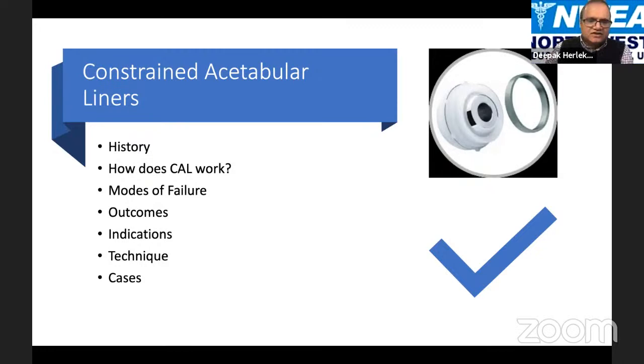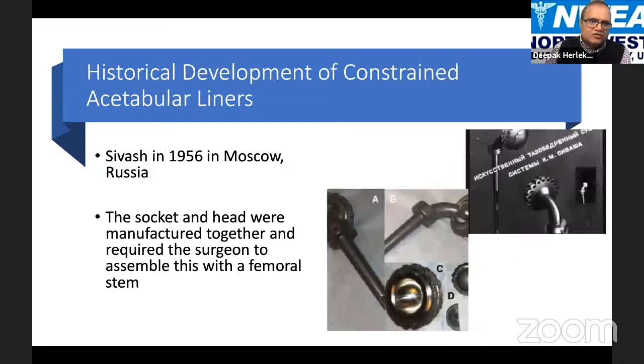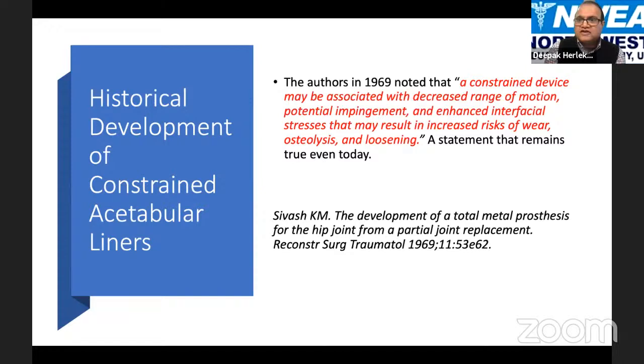The first reference about constrained liners was in 1956 in Moscow, Russia — an all-metal device where the socket and head were manufactured together, assembled with a femoral stem intraoperatively. The first publication was in 1969, and authors noted a constrained device may be associated with decreased range of motion, potential impingement, and enhanced interfacial stresses resulting in increased risk of wear, osteolysis, and loosening — a statement that remains true even today. Clinical use increased from the 1980s, and the modern design requires the surgeon to snap the head into the liner at reduction, with a locking ring secured around the rim of the liner.